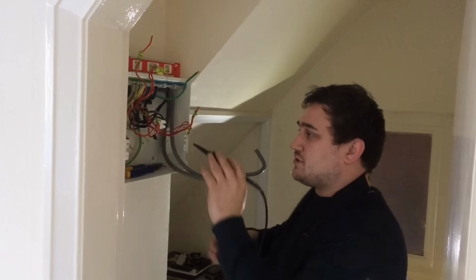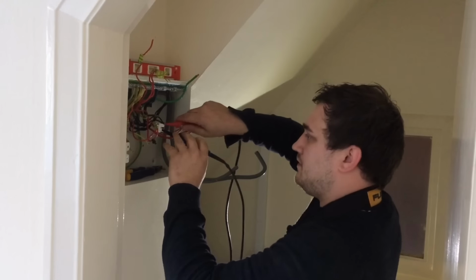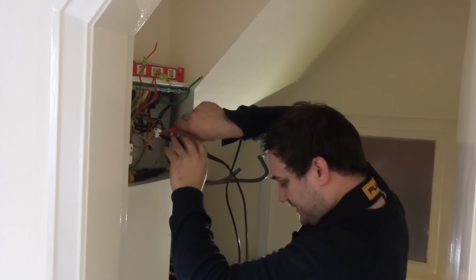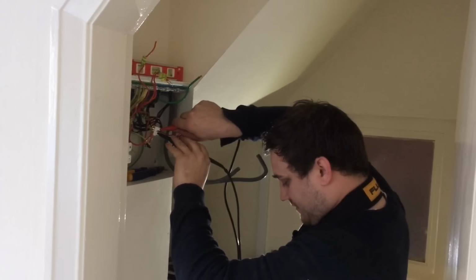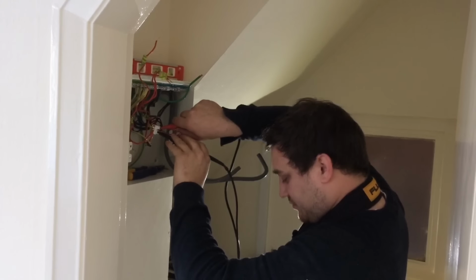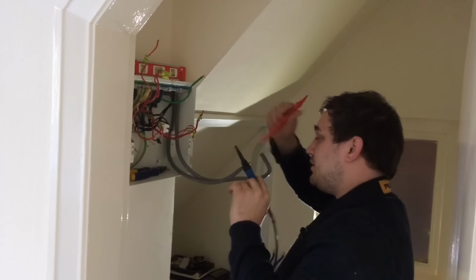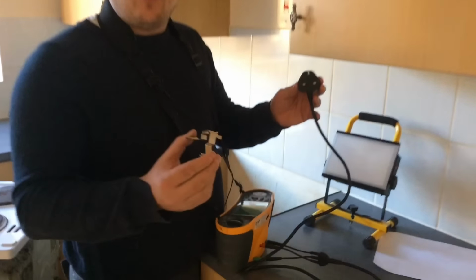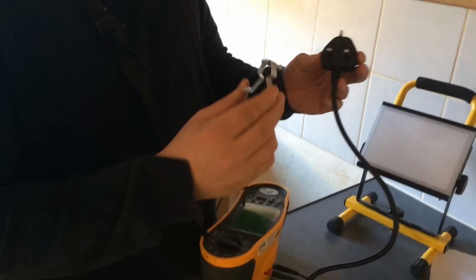I'm now going to test across the connector blocks to get a reading which should be within 0.05 of my calculated reading, which is 0.06, so it is. I'm now going to swap my leads over. I'm now zeroing out my plugged lead so I can carry on with my continuity of my ring final circuit and my figure of 8 test.